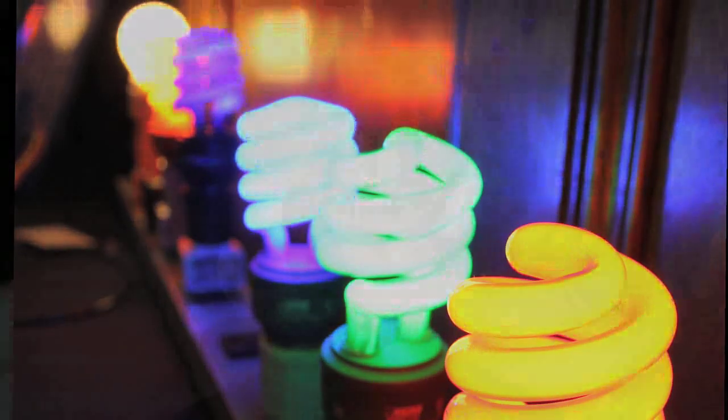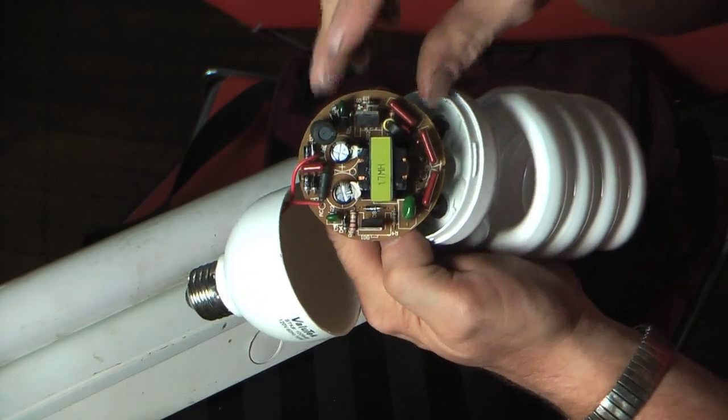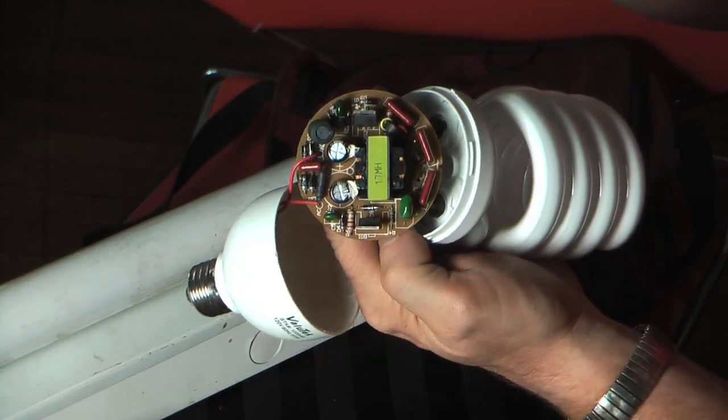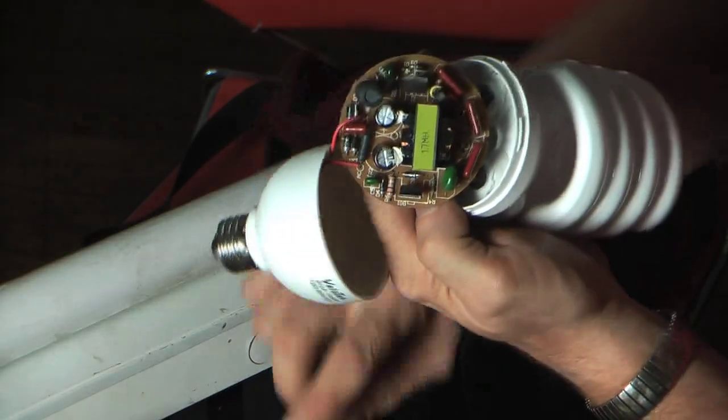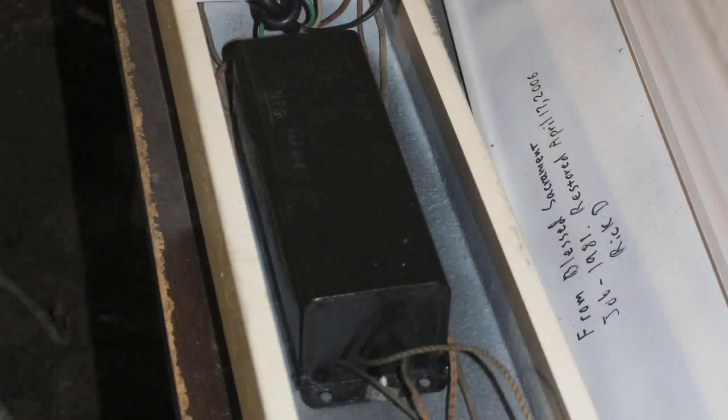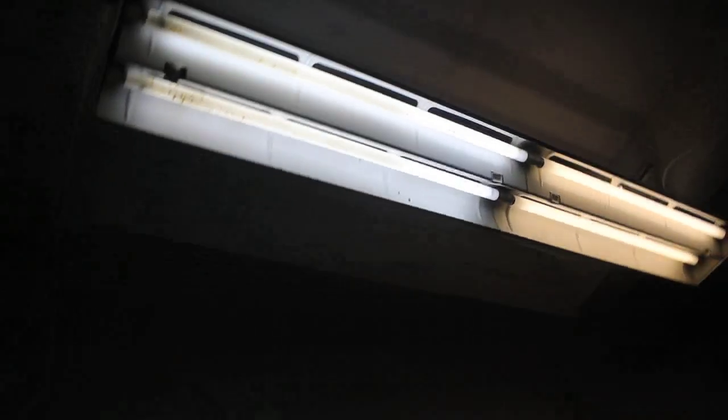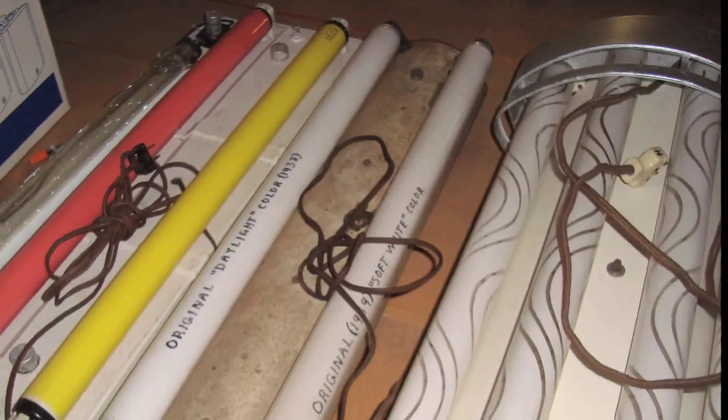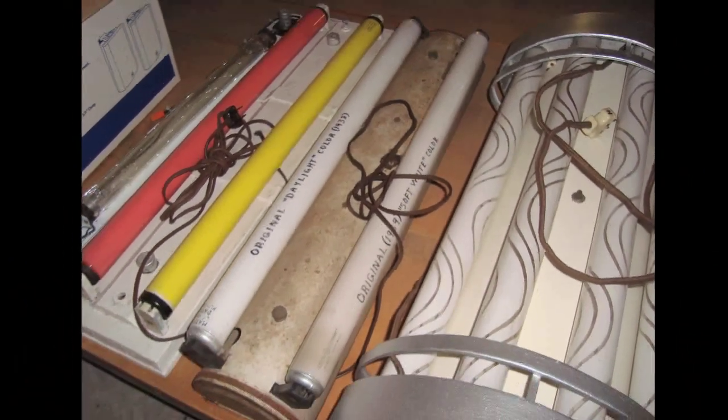And where a ballast, its efficiency is judged by how much losses it has. Because the ballast has to limit the current to the lamp and in doing so, some of the energy has to be lost in the ballast. It's just the laws of physics. So the losses of a ballast are expressed in watts. For example, a two lamp ballast like this one, preheat one, will lose about maybe 15 watts of power to run two 40 watt lamps. So that ends up being about 85 watts or so of total current consumption for the two lamps and ballast.